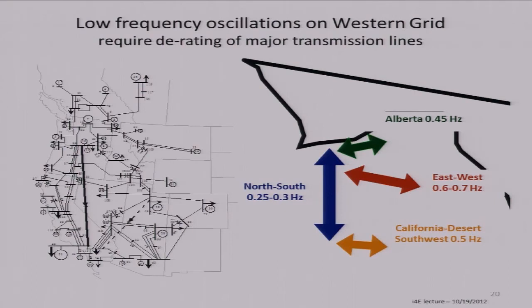But you still get the idea, which is that in this network there are characteristic frequencies of oscillations which are subsynchronous, slower than 60 hertz. So the north-south oscillation, which was the culprit in the previous slide, is at around a quarter hertz, so once every 4 seconds the power sort of sloshes back and forth.